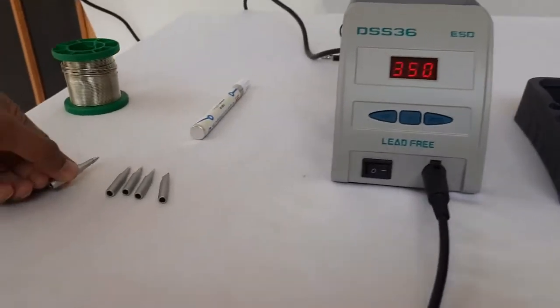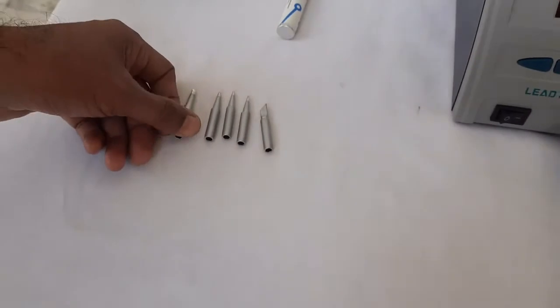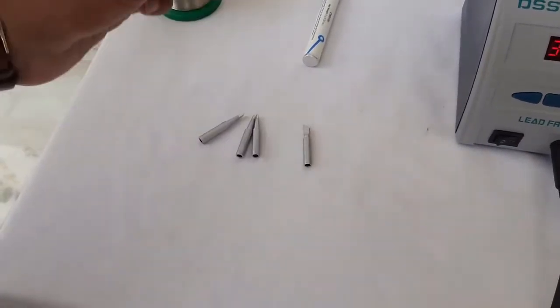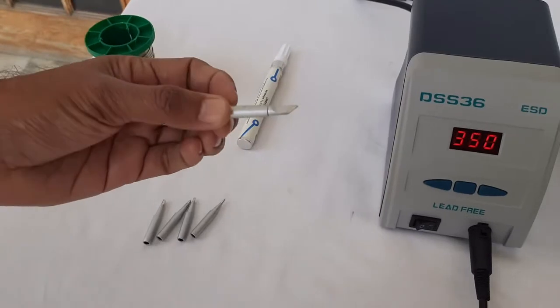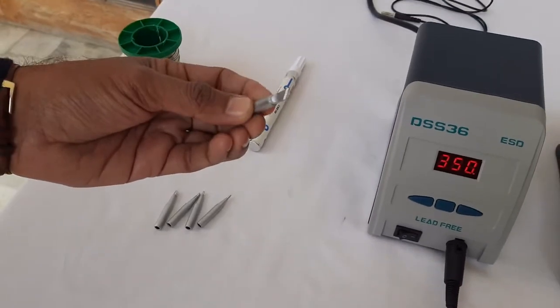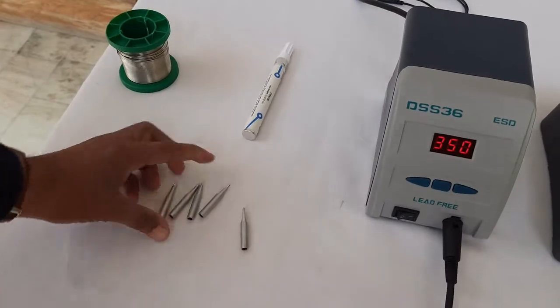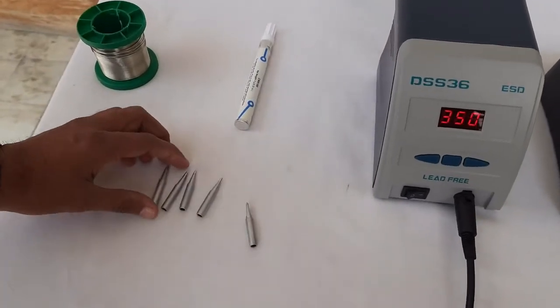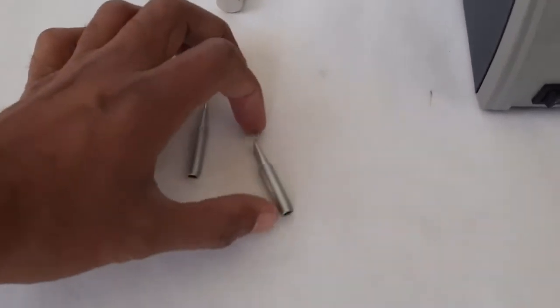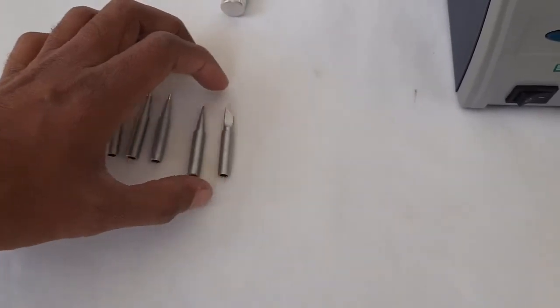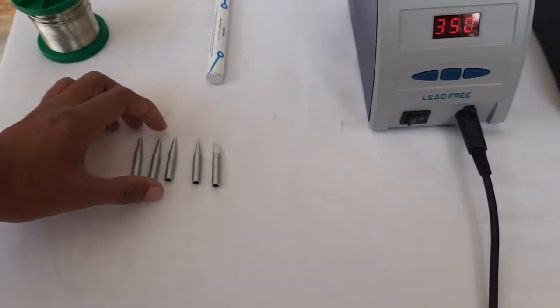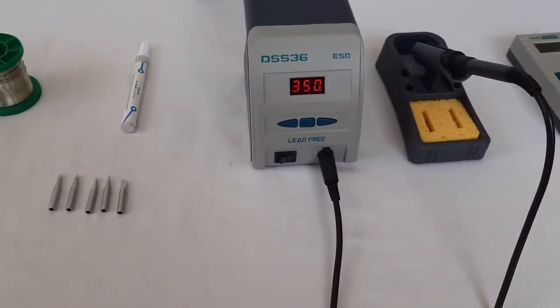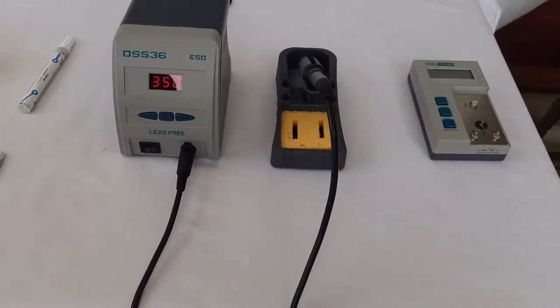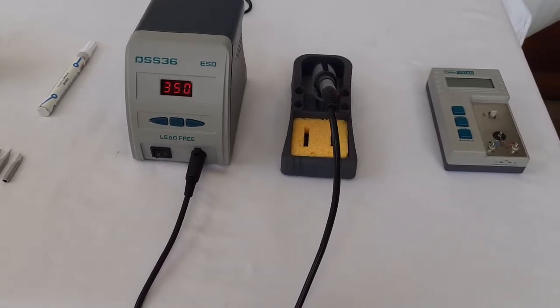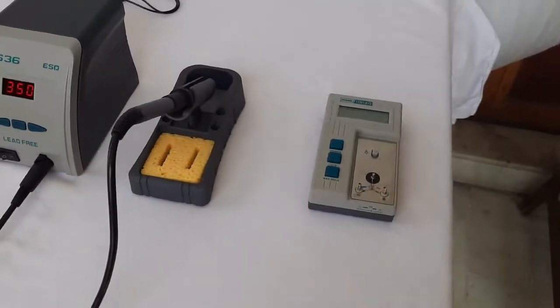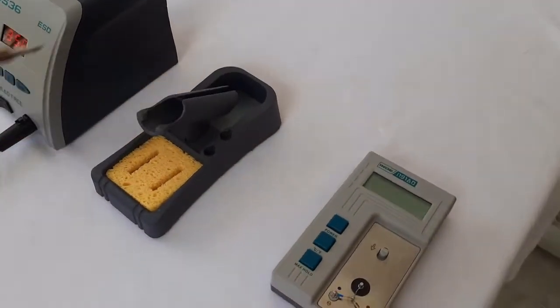Various types of soldering bits are available for this soldering unit, like chisel type, round type and knife type. This knife type soldering bit is specially used for SMD component soldering, and other bits are used for either SMD or through hole soldering. So this soldering unit can be used for both types of application, SMD and through hole soldering. Then we will move to the next step: we will measure the tip temperature and see if any variation is there between the set and actual temperature. Then we will calibrate this unit.